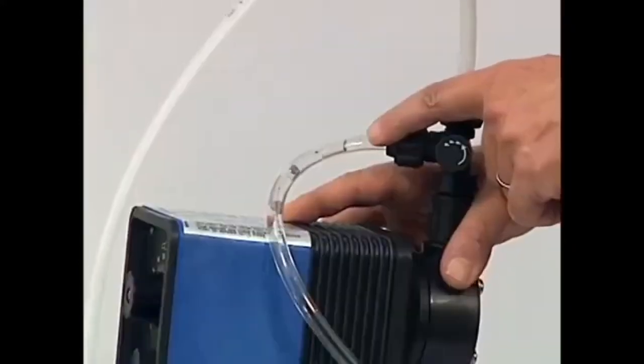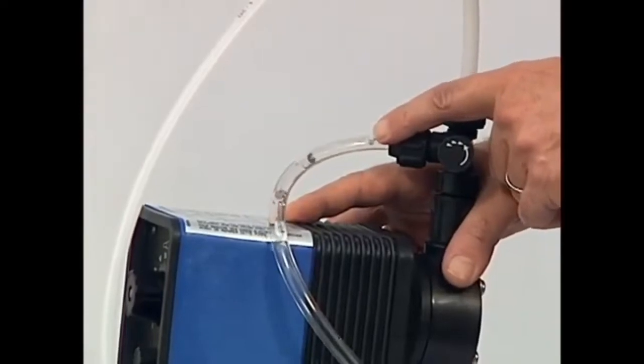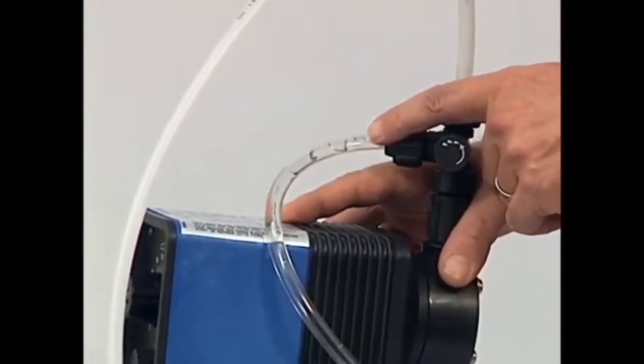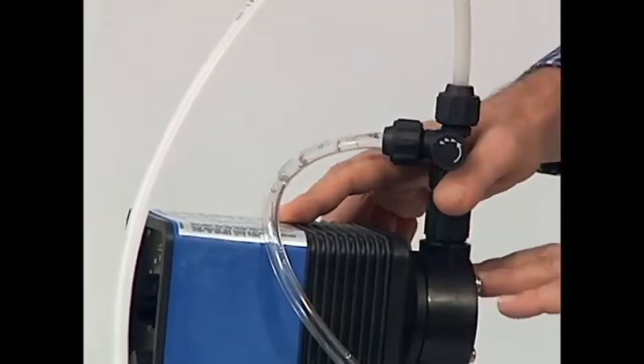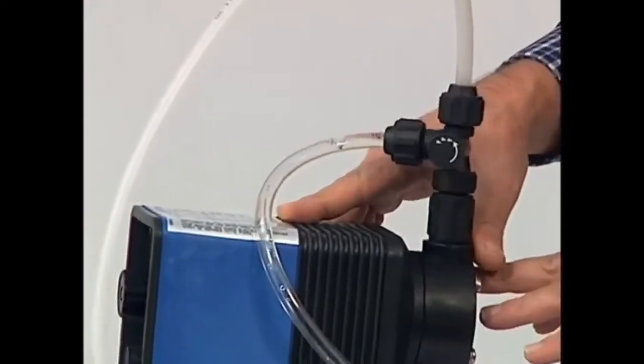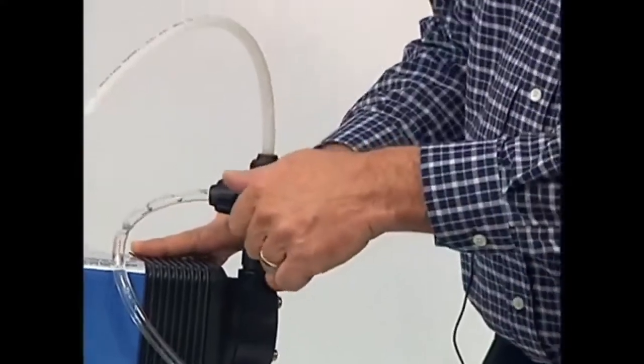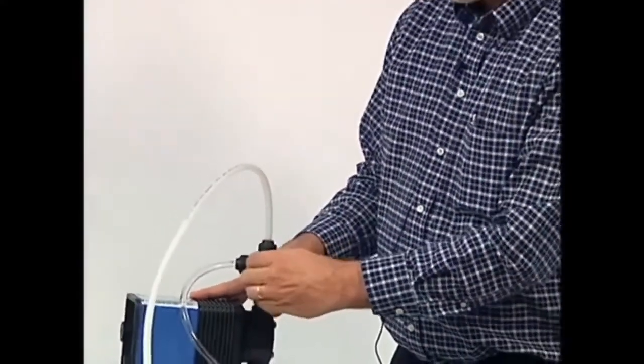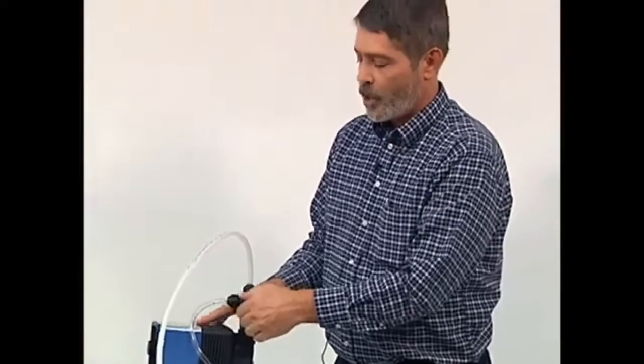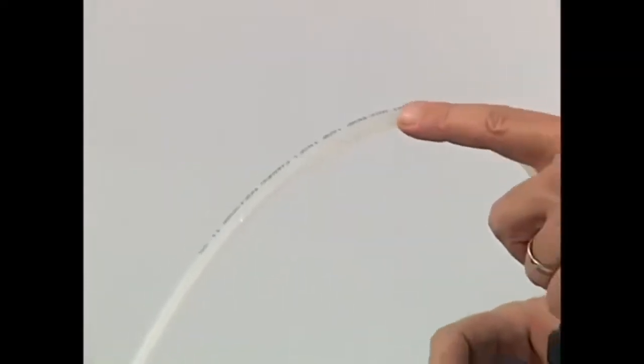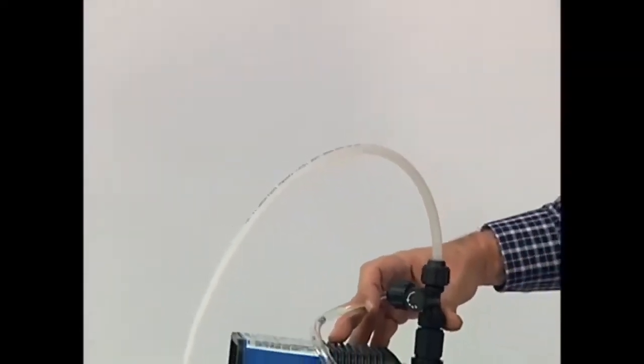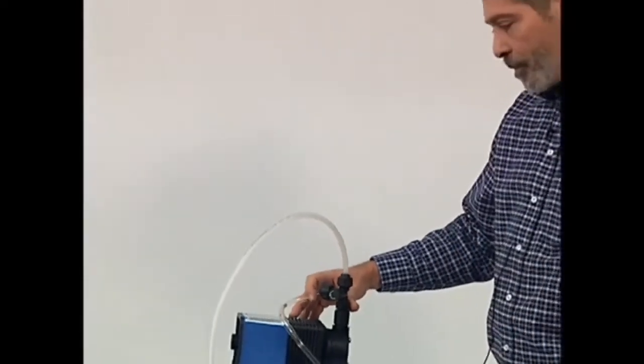As you can see, we're now beginning to get liquid returning back to the tank through our priming line. And this signifies that we have lifted the liquid to the diaphragm and the pump is ready to pump against pressure. At this point, you would simply close your priming valve, sealing off that avenue, and now your liquid will be forced through the high pressure tubing and into your customer's system. And again, on the first time, you'll be able to see the air bubbles and things move as the system actually primes and begins to get chemical for the first time.